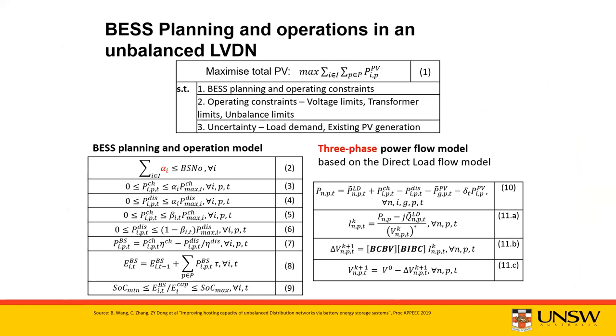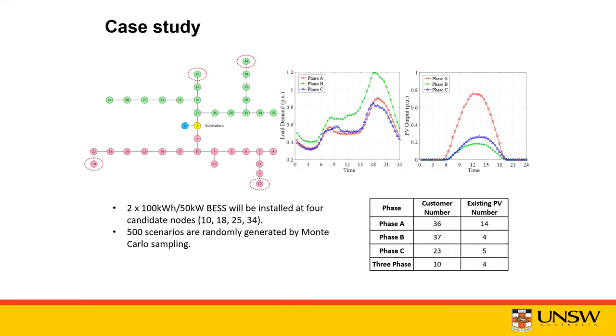Very quickly, given the timing, we try to maximize the total PV that can be installed to the network, subject to BESS planning and operating constraints, and also the uncertainty involved in the system, using a three-phase power flow model. This is a case study based on real system data. As you can see in the figure, for three-phase load, the load demand in phase B is much higher than the other two phases. For the same feeder, the PV output is highest in phase A, while phase B is smaller, which explains itself - phase A with PV generation can offset some load, but it's still very unbalanced.